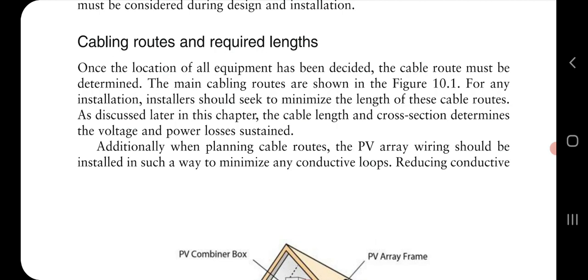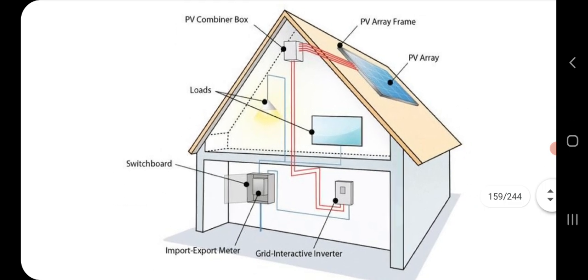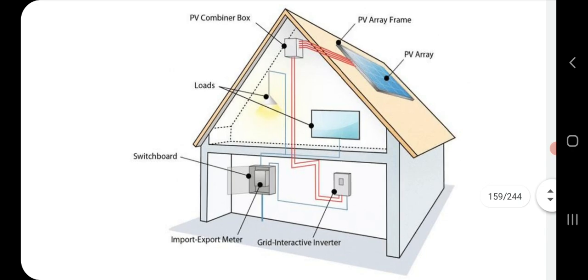Now in this one we will see a house. In this house, the PV array is mentioned, and the PV combiner box. The cable goes from the array to the combiner box, then to the grid interactive inverter, and from there it goes to the house, as well as to the grid, or directly from the inverter it goes to the import export meter, and depending on that it goes to the house and to the grid. The cable you are seeing in red has to be taken care of, the length has to be calculated, and maximum care has to be taken that the route or the length of the cable is reduced.